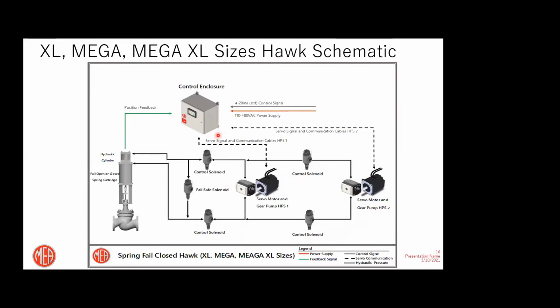We see there is a deviation, and we tell our motor to run one way or the other. So we open the solenoid valves, we start pumping the fluid from one side and dumping into the other. After repositioning, we close these solenoid valves. Whenever we need to go the other way, it just goes the other way. And it just goes back and forth as many times as we need to.